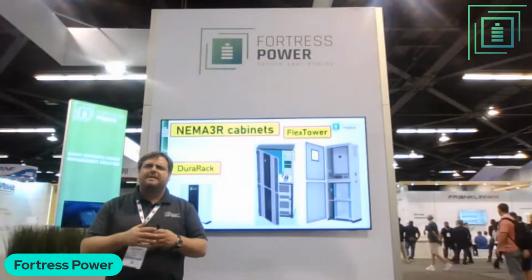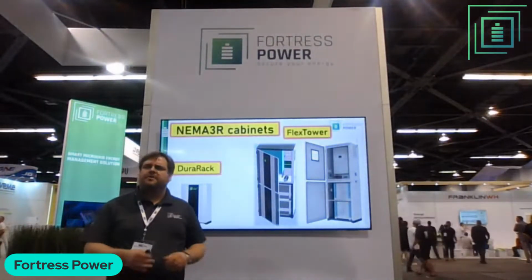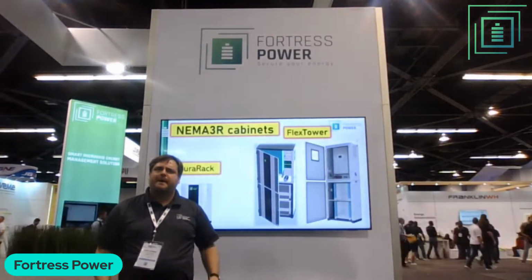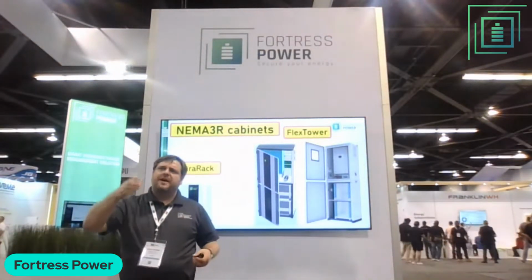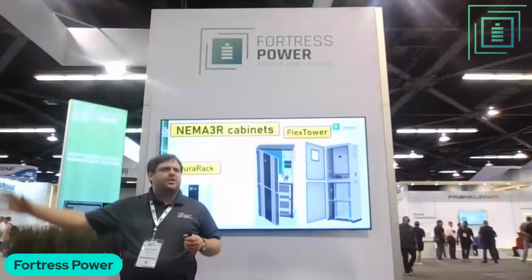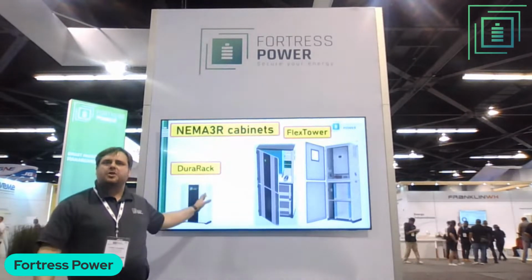That eliminates your wiring trough and conduit, especially with modern day 48-volt battery inverters that have 200 amp grid pass-through. Your project can be as easy as pouring a concrete pad right by the meter, putting the Dura-Rack down, putting the eFlex in it, putting the Flex Tower on top, no wiring troughs, no conduit, one stub of wire up into that inverter. So you just come in from the utility meter and you go out to your load center. This is independent of whatever condition the wall is in.